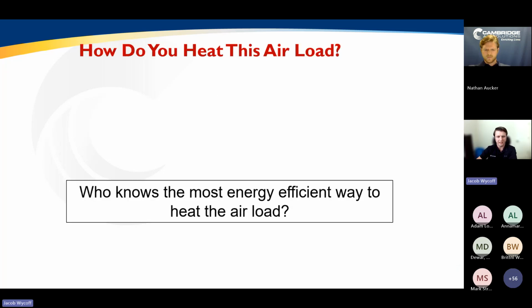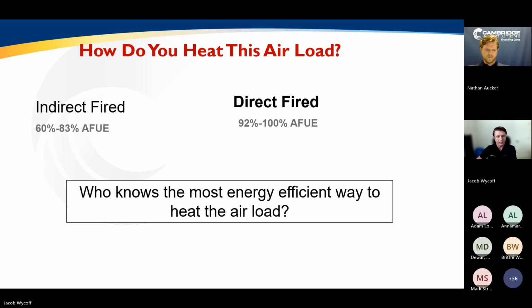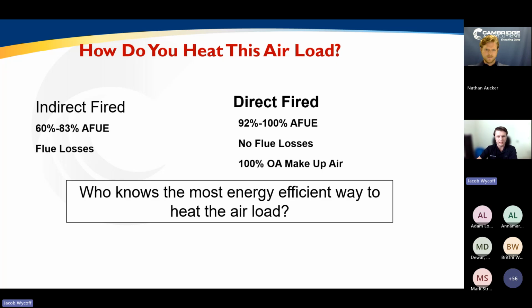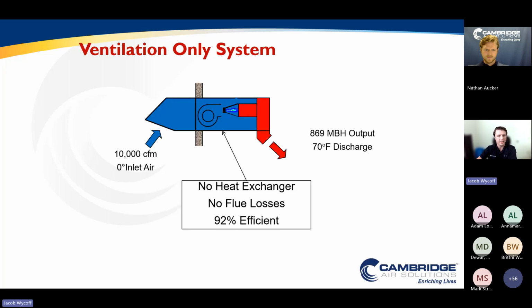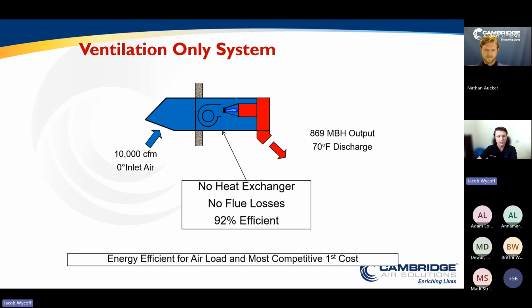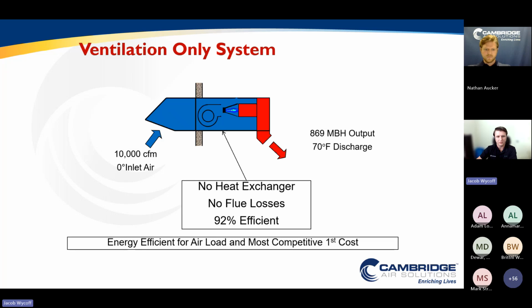So what's the most efficient way to heat the air load? We know this, especially from kitchen applications, to be direct fire. Those are very cost sensitive applications, and they definitely want the most cost effective and energy efficient way to heat the air load. Pretty clearly, it's going to be direct fired because of its improved efficiency and improved simplicity over indirect fired technologies. It has no flue losses, and it's going to require 100% outside air makeup air, but that's fine because in this instance, we're only talking about air load. So let's take this example of 10,000 CFM of 0-degree air entering the unit and discharging at 70 degrees. This is the most energy efficient and most competitive first cost way to heat an air load. Remember this example because we'll come back to it in a couple slides.